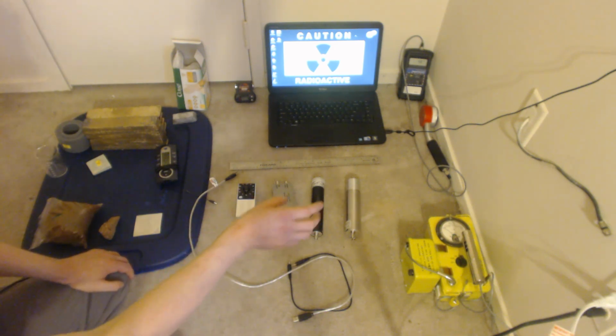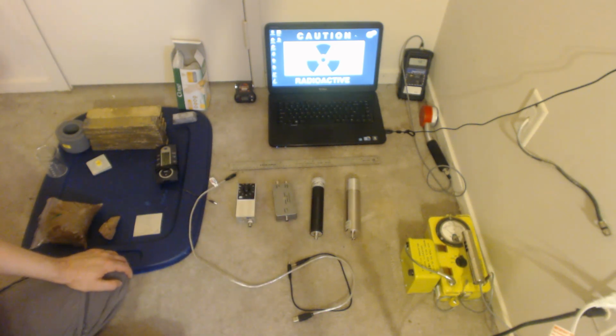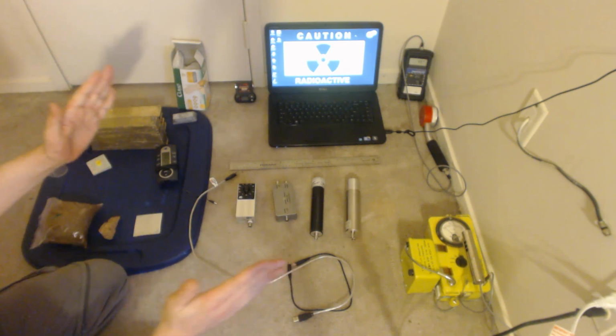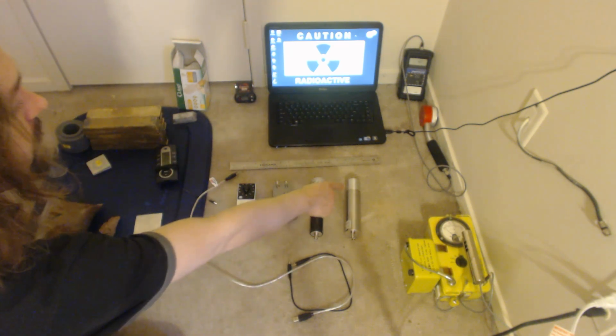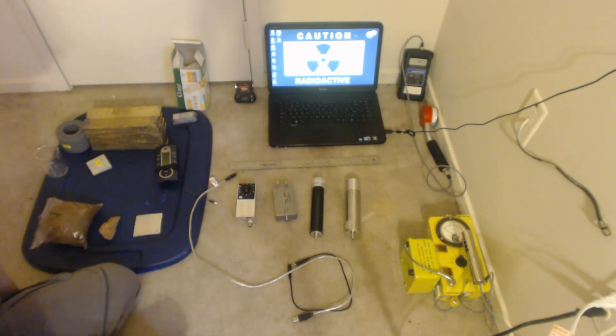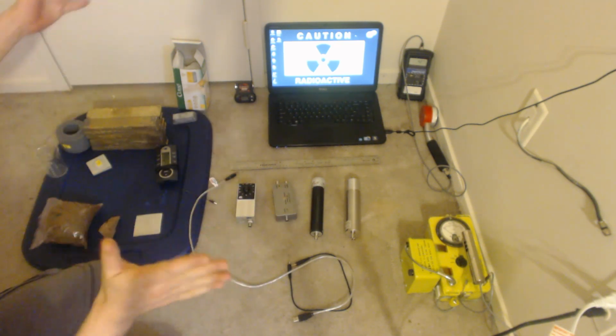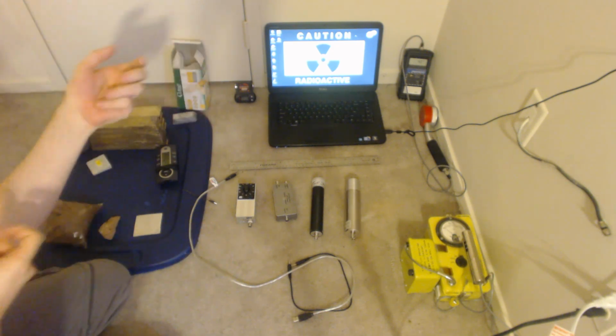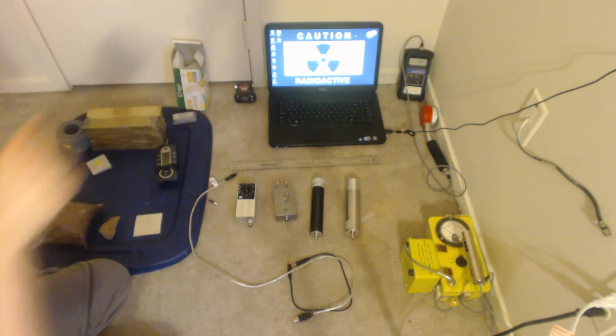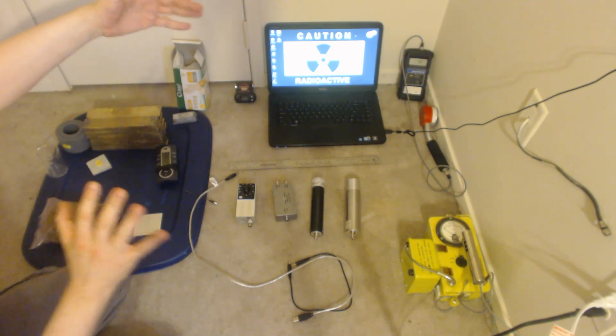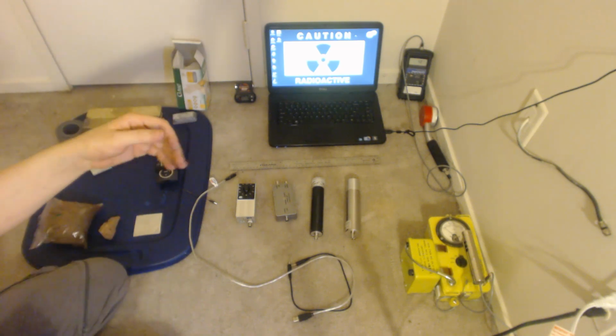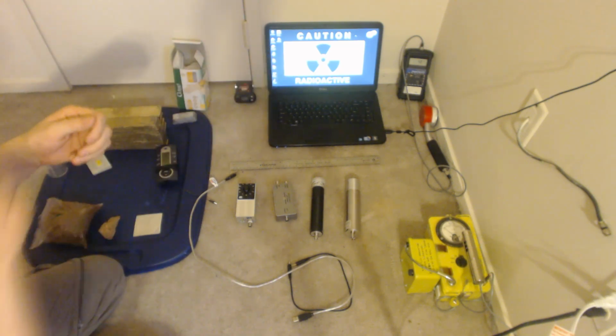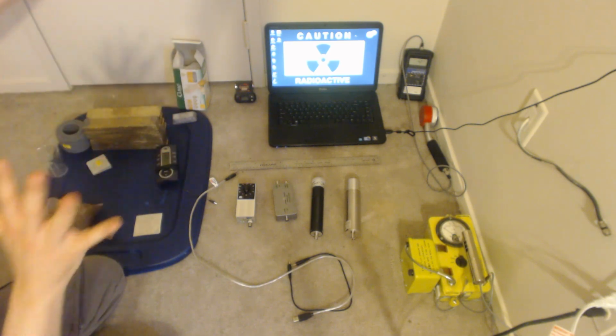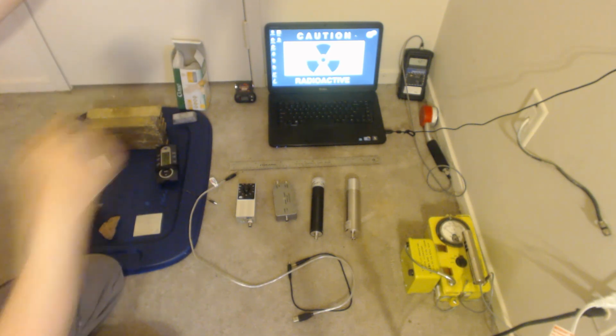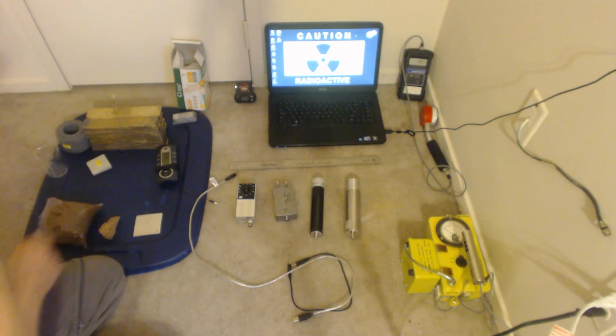Now, the next thing to know is the size of the crystal, because with gamma spectroscopy, size does matter. The sodium iodide probe here is a 1.5 inch. The crystal's 1.5 inches thick. Now think about a bunch of trees, and think about somebody shooting a gun. The gun is the radioactive material, the bullets flying out are the gamma rays, okay? So if you have a bunch of trees and the trees represent the crystal, if the trees are really thin, just a few trees, it's very likely the bullets will go right through and not hit a tree, right? But if there's lots of thick trees, then it's more likely the bullets will stop when they're hitting the trees. They won't make it all the way through.